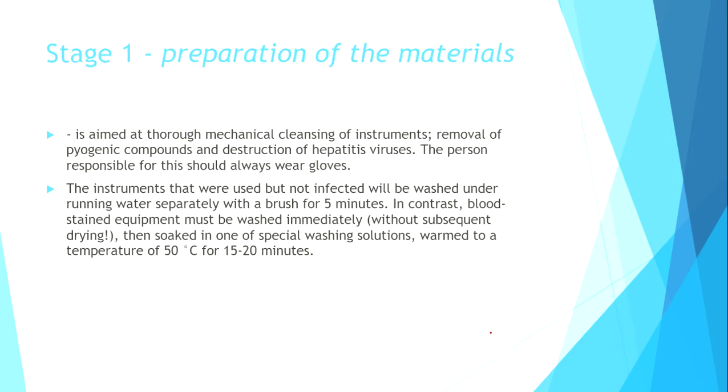Stage 1, preparation of the materials, is aimed at thorough mechanical cleansing of instruments, removal of pyogenic compounds and destruction of hepatitis viruses. The person responsible for this should always wear gloves. The instruments that were used but not infected will be washed under running water separately with a brush for 5 minutes. In contrast, blood-stained equipment must be washed immediately without subsequent drying, then soaked in a special washing solution warmed to a temperature of 50 degrees Celsius for 15-20 minutes.